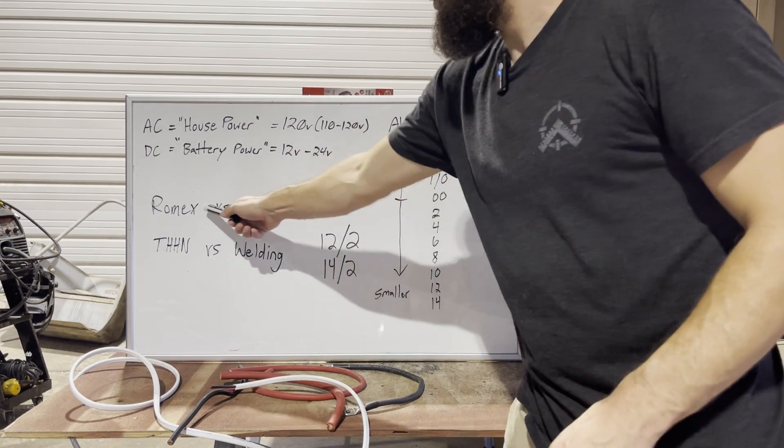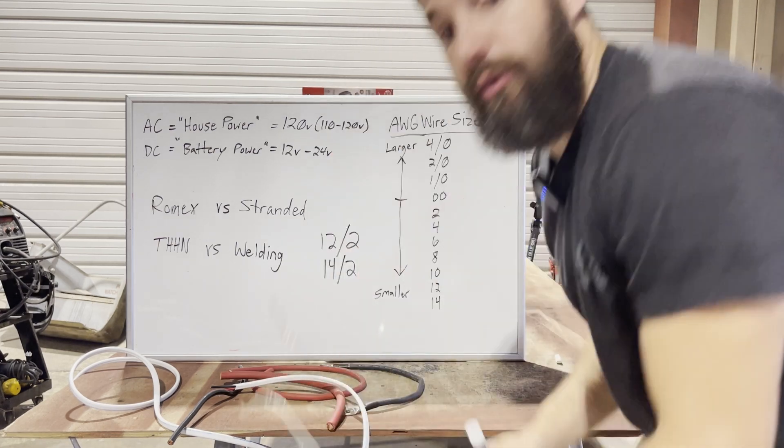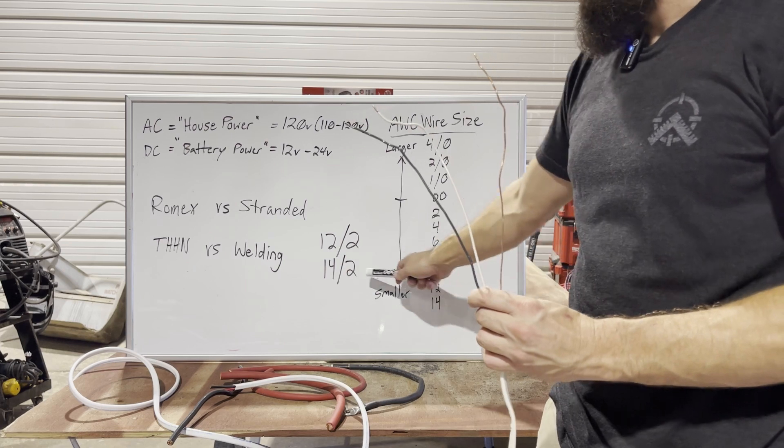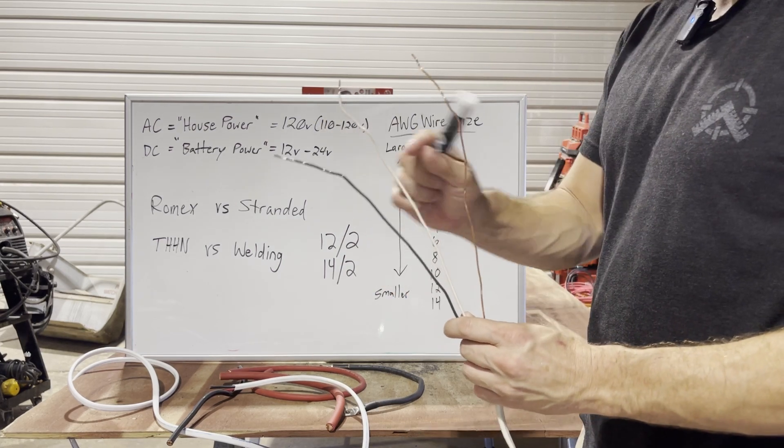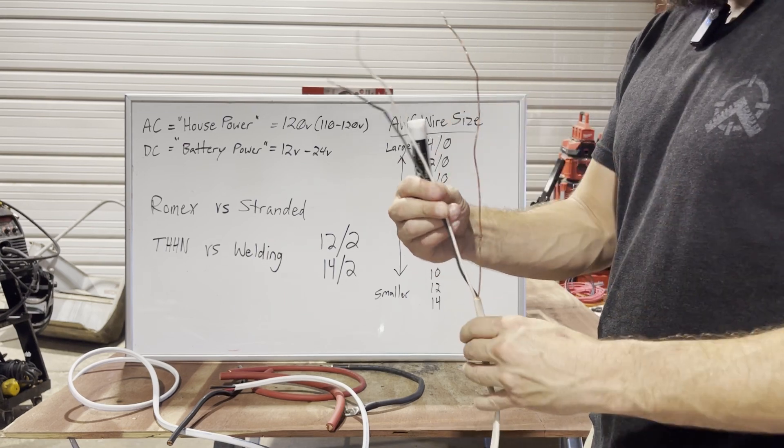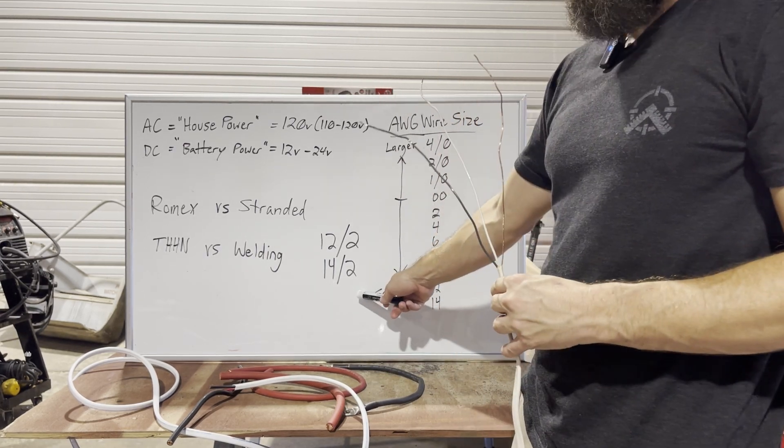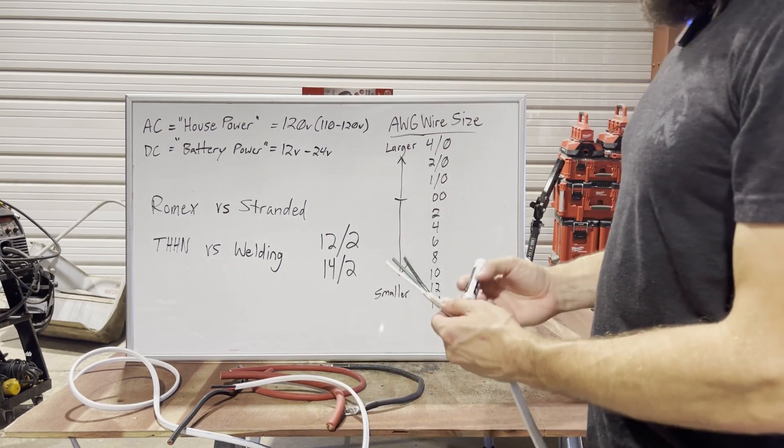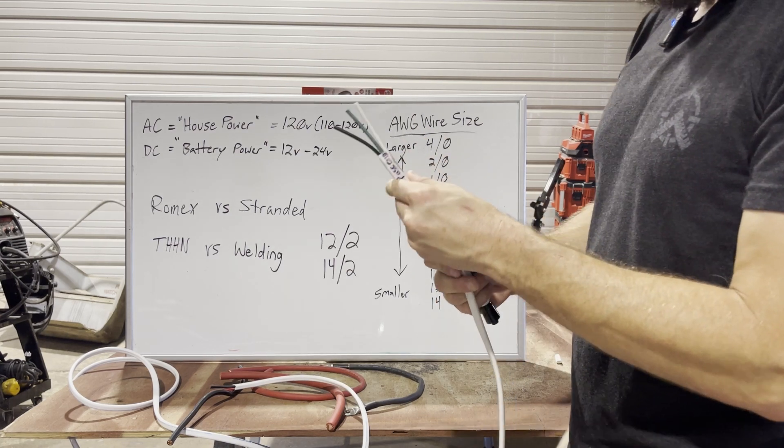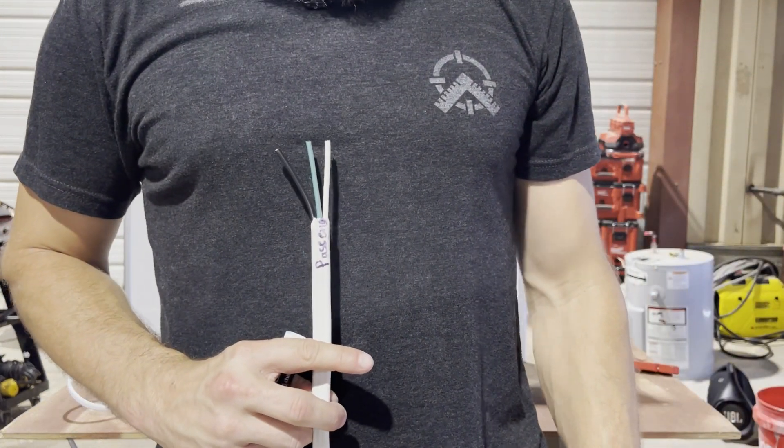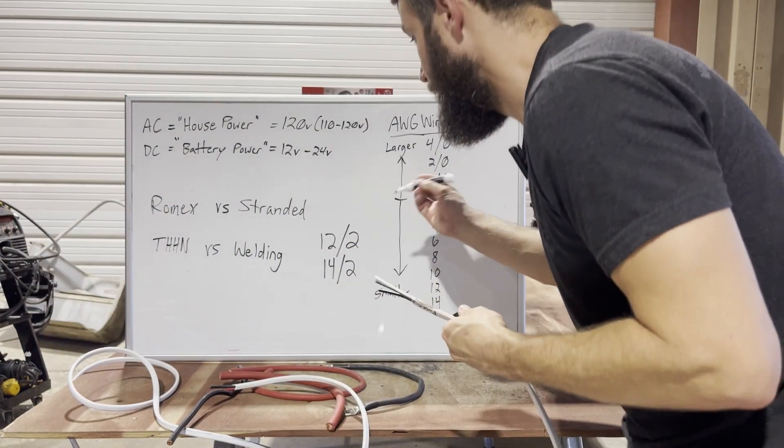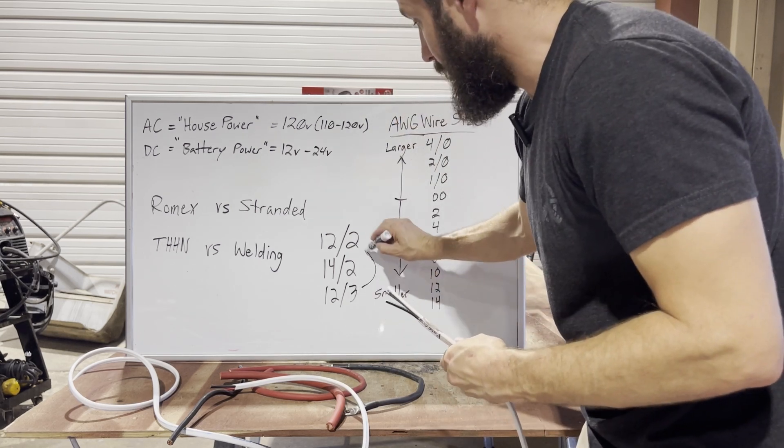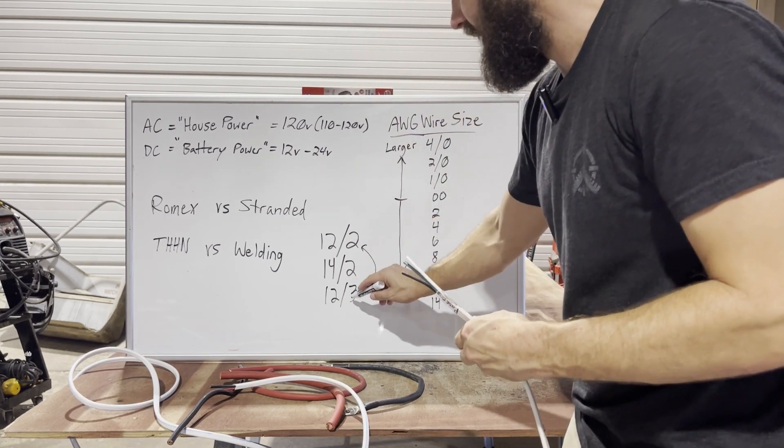But when you get into Romex versus stranded, Romex being your typical residential solid copper like this, this is a 14-2. That's going to be on the smaller wire size for AC power. It is three wires or two wires and a ground. They call this 14-2, 14 being the wire thickness, two being the number of wires, but they're not counting the ground as a wire. When you get into stranded, the Marine stranded like this, you're looking at three wires. They're counting the ground as one.